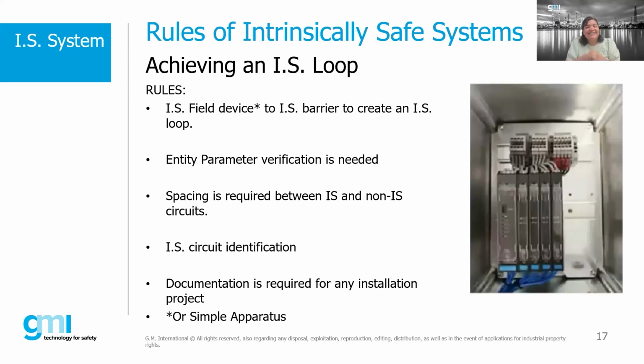IS circuits need to be easily identifiable. We normally think about IS with light blue, which is fine as a way to identify, as long as there's nothing else in your installation with that same color. But it doesn't have to be light blue - you can also just put labels, but it needs to be easily marked to inform people in the field that those IS circuits cannot touch non-IS circuits.